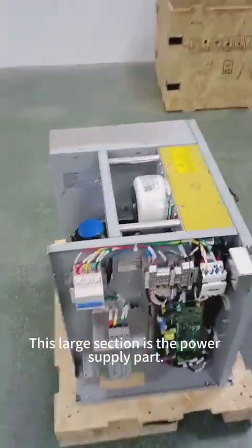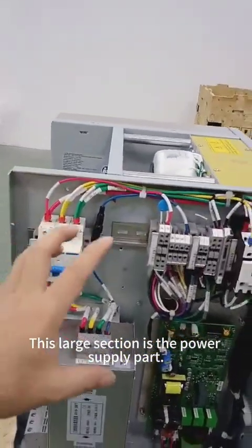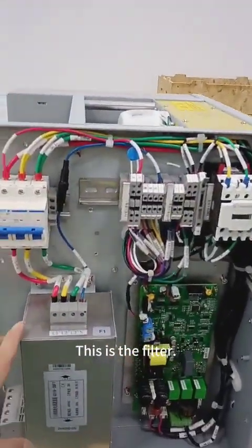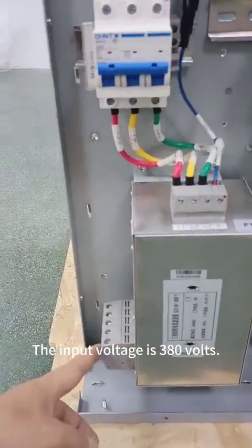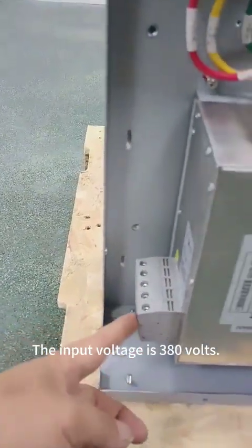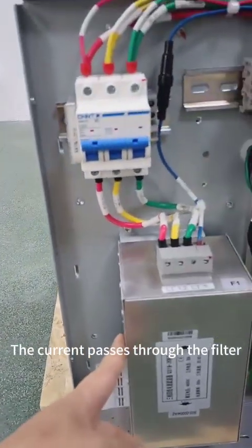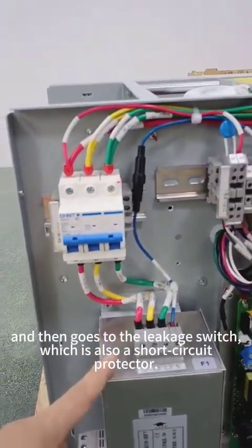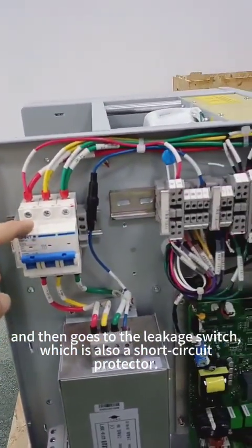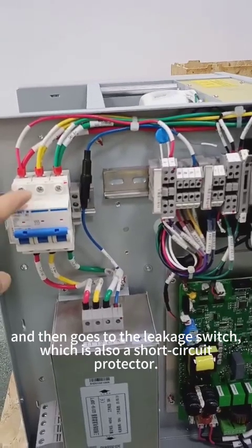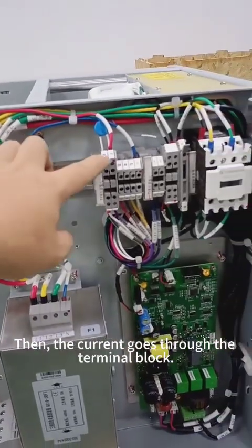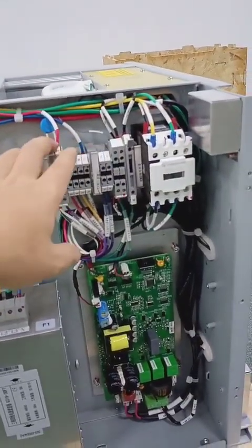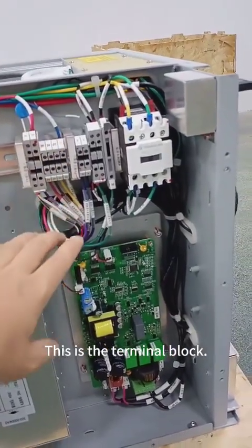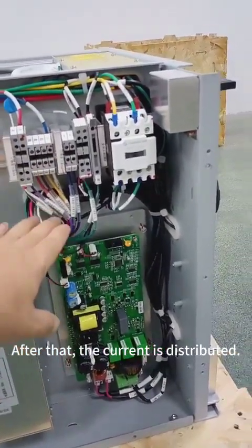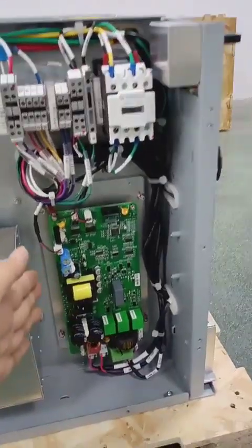This large section is a power supply part. This is the filter. The input voltage is 380 volts. The current passes through the filter and then goes to the leakage switch, which is also a short circuit protector. Then the current goes through the terminal block. This is the terminal block. After that, the current is distributed.